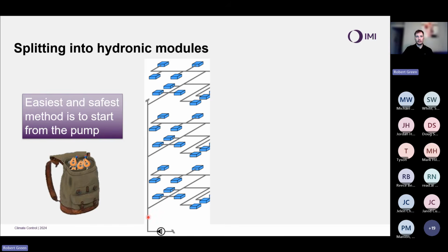The first thing we want to do is place a main balancing valve by the pump. Now, you might say to me, yeah, Rob, but I thought we said we want to only add the absolute resistance we really need. Why are we putting a valve in series with the pump? Because we could just adjust the pump. But that is a key point to put there because it simplifies our commissioning and allows us to do fine adjustments and measure the total flow in the system.